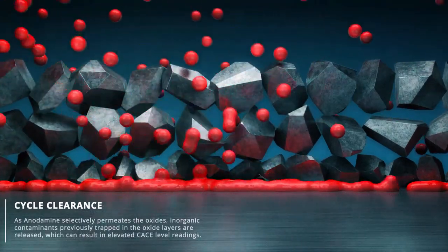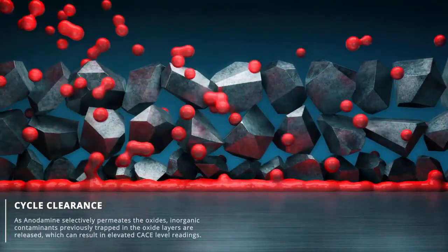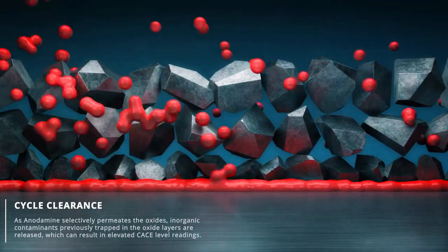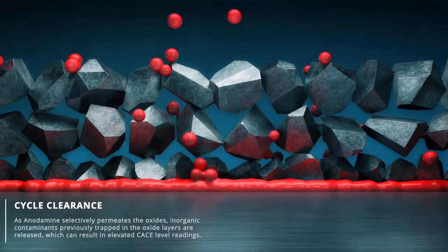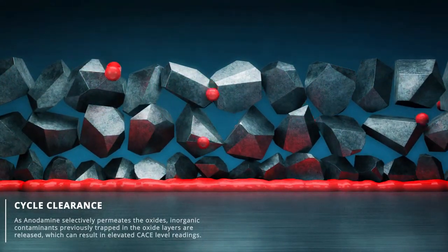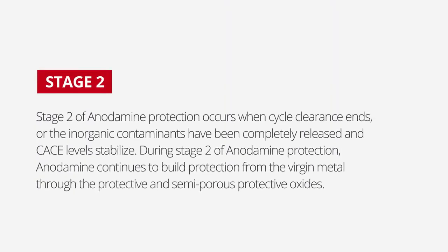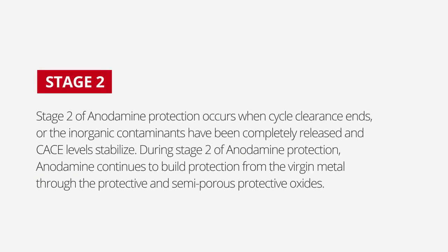It is important to note that base metal protection is achieved throughout the cycle during stage 1 with proper OEM compliance. Stage 2 of Anodamine protection occurs when cycle clearance ends, or the inorganic contaminants have been completely released and CACE levels stabilize. During stage 2 of Anodamine protection, Anodamine continues to build protection from the virgin metal through the protective and semi-porous protective oxides.